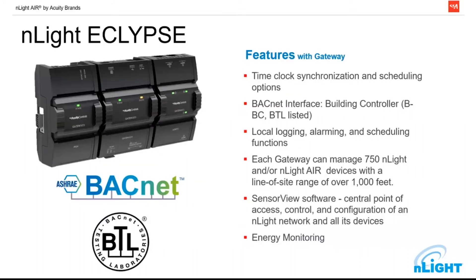That little black box — the Eclypse. The main features important for a contractor or building owner to know: it gives us our astronomical time clock, ability to add schedules, preset themes, different profiles based on time of day, and also our BACnet interface. So we are able to build a building automation system. The BAS can listen to our sensors and write some data as well. That's included for free with our Sensor View software, which also comes free with this Eclypse backbone device. It also gives us the ability to do some energy monitoring.